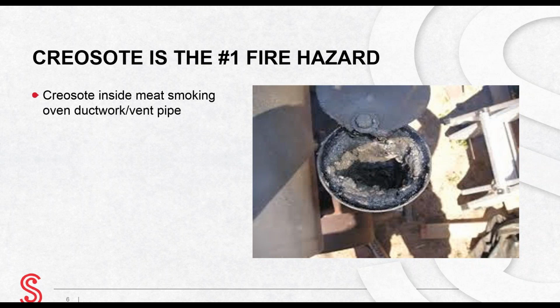All it takes to ignite creosote in hoods, filters, and ductworks is a spark, burning ember, or flame that raises the creosote temperature to 165 degrees Fahrenheit. The role of grease as fuel in commercial kitchen fires is also well known. The combination of creosote and grease is easier to ignite than creosote alone, and it burns hotter than creosote does alone. These fires start quickly and spread very rapidly.